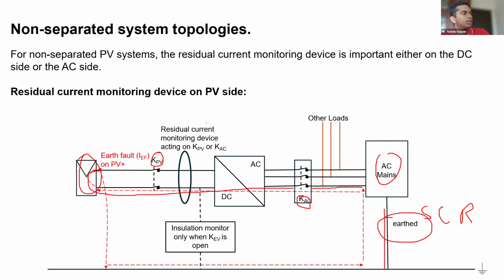And one more thing is, this residual current monitoring device can be put either on the AC side or on the DC side. Here it is actually present on the DC side. It can also be on the AC side; I'll explain in the next slide. And one more thing is, an insulation monitor is also mandatory here, because it is mostly kept inside the inverter. So when this trips, if the KAC or KPV is disconnected, this insulation monitor will check the insulation between the conductors.